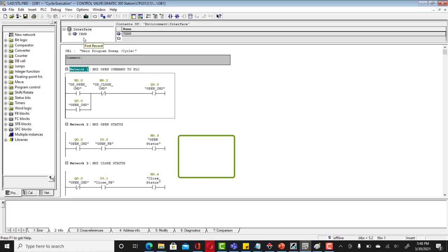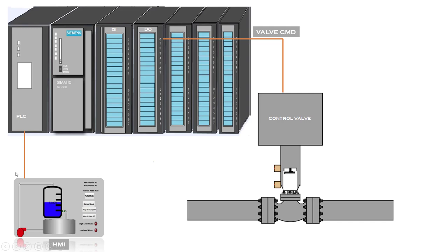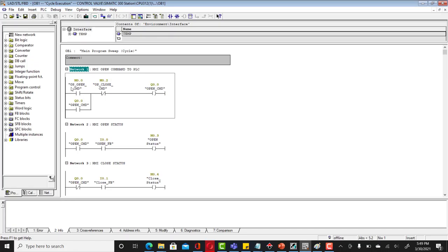Now I'm going to show you how the program of a control valve for on and off control valve looks like. We have an open command that is coming from HMI that would be linked to your PLC. When the operator presses that open command, this would turn high and that would activate your open command here. This is the operator open command. This one is coming from HMI and this one is actually going from a PLC to a control valve.